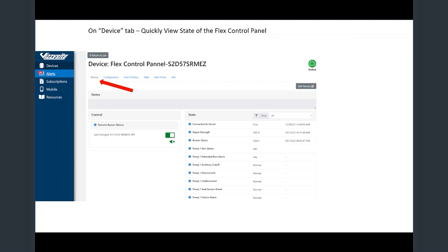It gives you your pump status, and if you have an extended run alarm or your auxiliary cutout fail-safe in there, we can have it cut off your pump if your seal fail or your thermal is activated. With our Flex system, if you're over current, we can also deactivate your pump there. So it's kind of, we can't market it as an overload protection, but use your imagination.